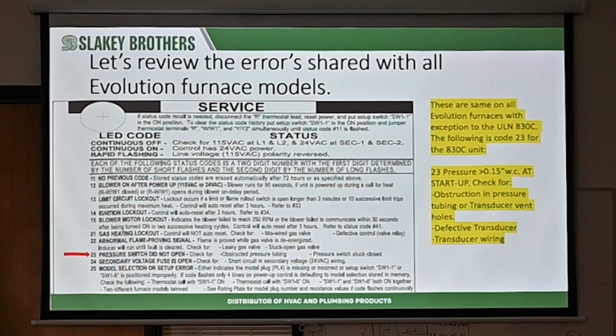Okay? 22, you'll find that everywhere. Abnormal flame proving signal. Flame is proved while a gas valve is de-energized. What that means is the flame sensor or the board is receiving micro voltage stating that there's a flame there. But I don't want heat on. I just turned the heater off. The board is thinking it should be off, but it's sensing a flame there. So all you got to do is go look at it.